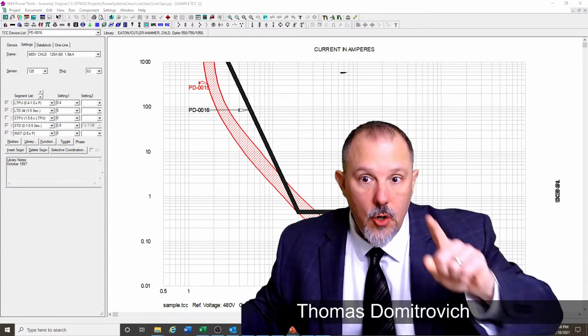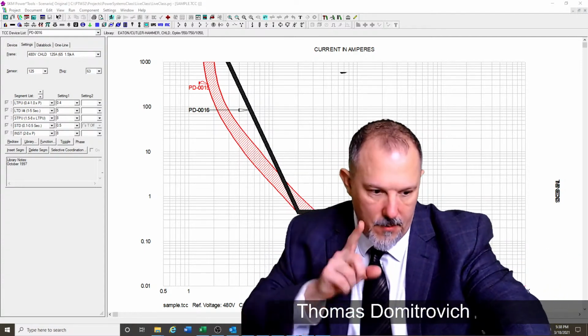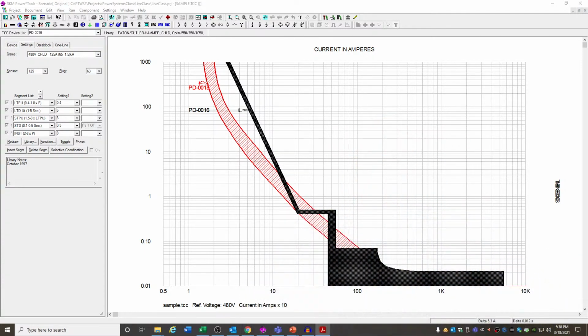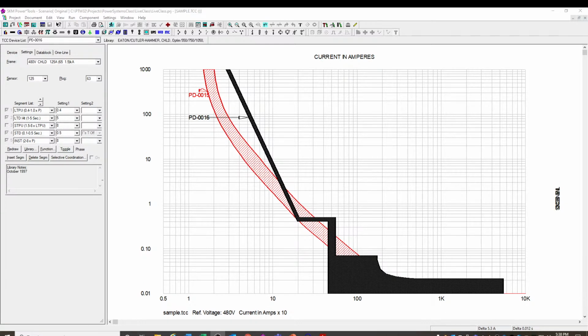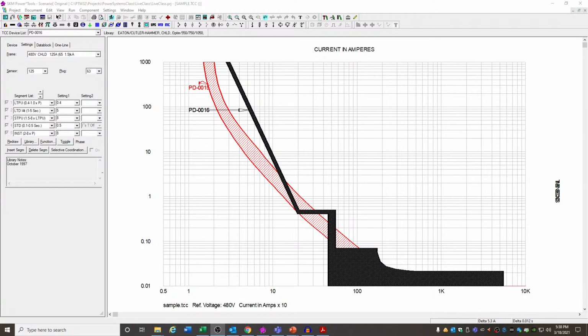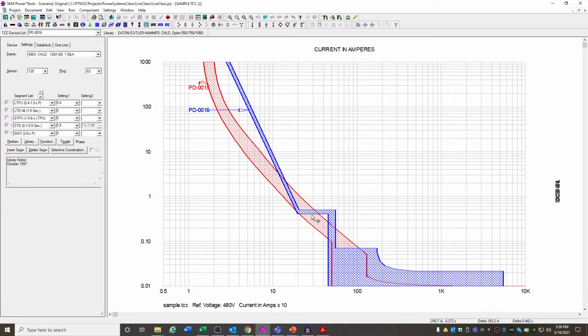So the instantaneous region is no intentional delay. Remember that, no intentional delay. If you look at this trip curve, look at the black curve on here. And if you're colorblind, then it's the one that has the diagonal. It's not the swooping color. All right, now it's the blue curve. Now it's the black curve.